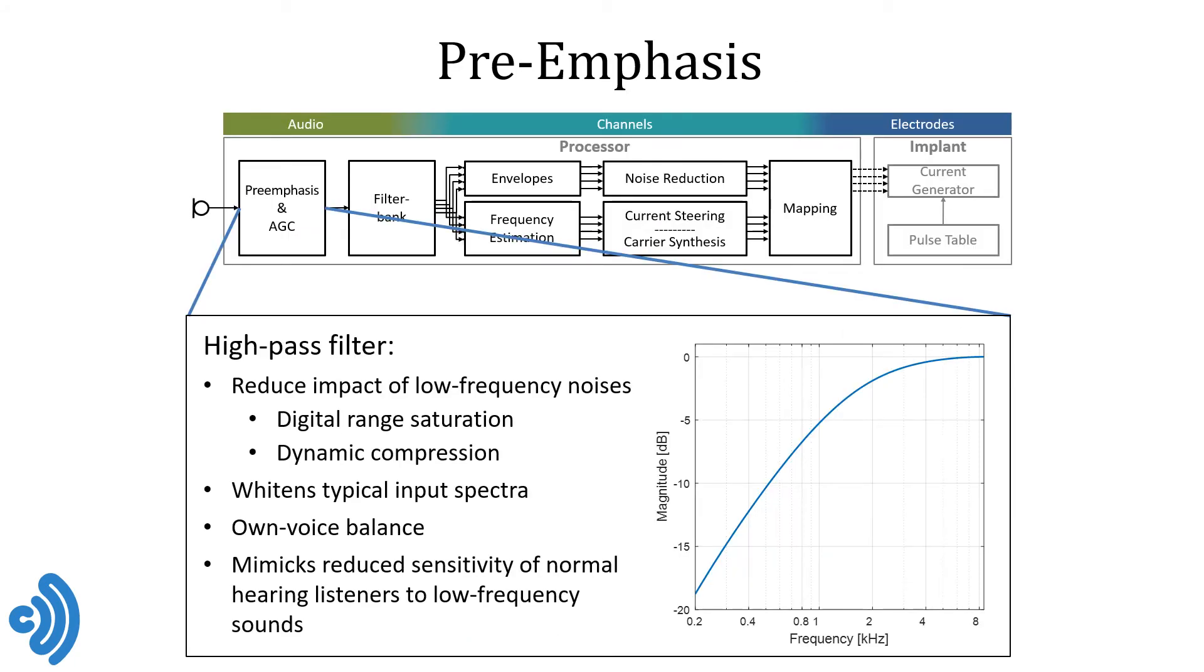The very first step in the processing chain is to simply apply a high-pass filter to the audio input, which we call pre-emphasis. The magnitude response of the filter is shown on the right and you can see that we have around 10 dB of attenuation at 500 Hz, 5 dB of attenuation at 1 kHz, 2 dB remaining at 2 kHz and so on. The purpose of this filter is to reduce the potential negative impact of low frequency sounds and environmental noise on the further processing, potentially causing saturation of the AD converters or triggering dynamic compression. It generally whitens the spectra of speech and other low frequency dominated sounds and helps with balancing the perceived loudness of the CI user's own voice. Finally, it also mimics the reduced sensitivity of normal hearing listeners to low frequency sounds.